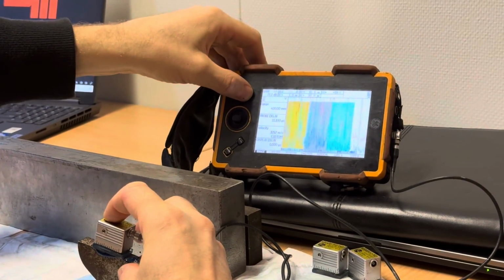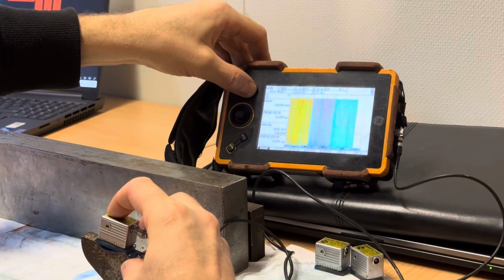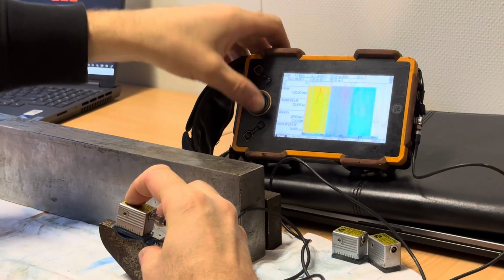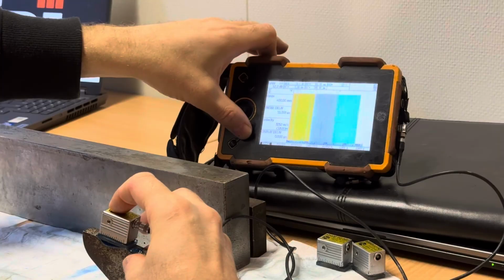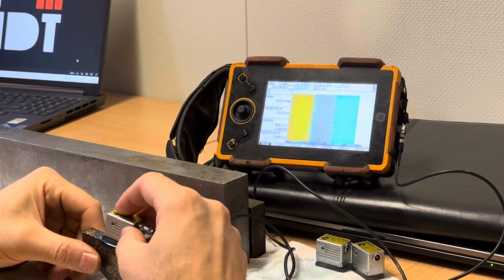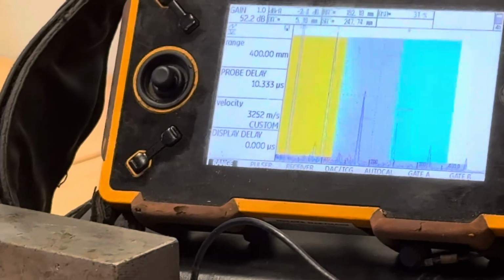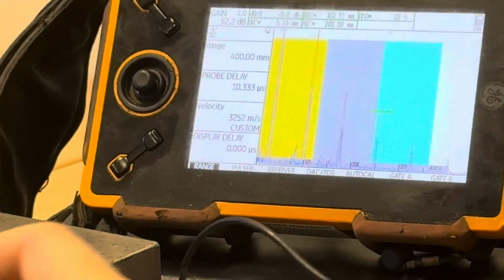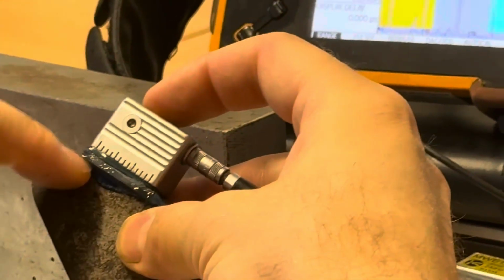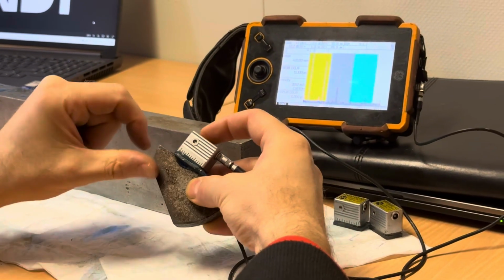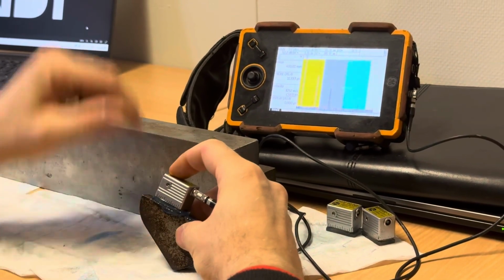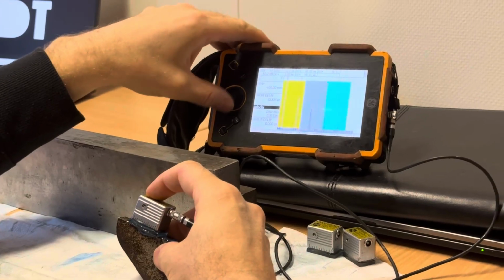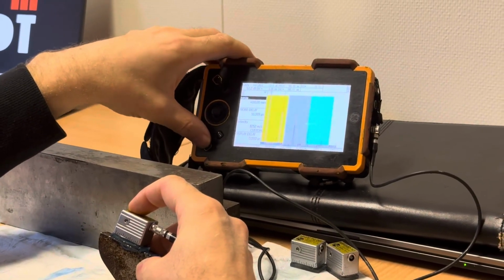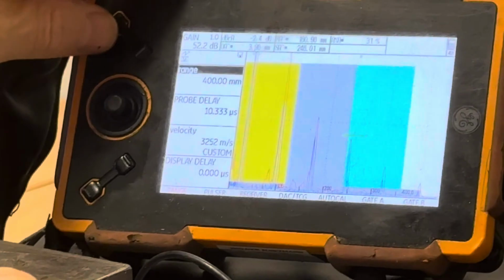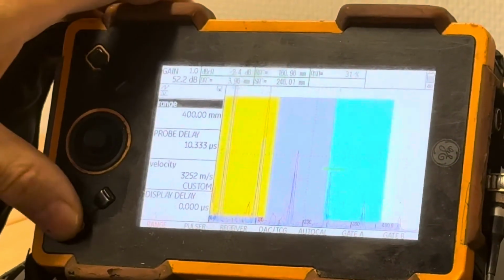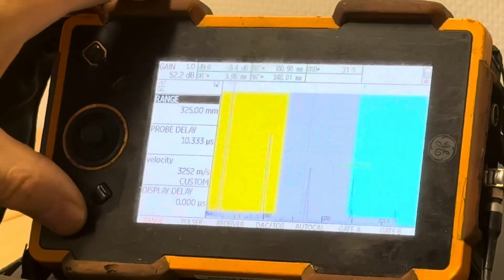There's a lot of noise. So we select accordingly. Here we find the first signal. The first signal is we have 25 millimeters. So this radius is 25 millimeters. We successfully identify and locate the very first signal. So in this particular case, the overall range is very large. We then proceed to carefully reduce the operational range.